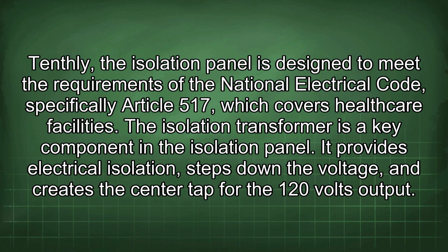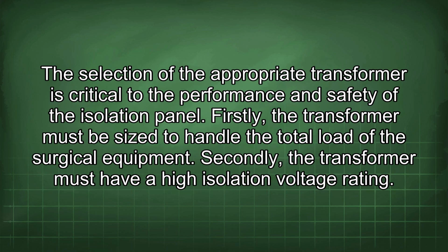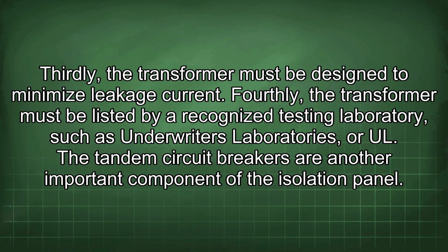The isolation transformer is a key component in the isolation panel. It provides electrical isolation, steps down the voltage, and creates the center tap for the 120 volts output. The selection of the appropriate transformer is critical to the performance and safety of the isolation panel. Firstly, the transformer must be sized to handle the total load of the surgical equipment. Secondly, the transformer must have a high isolation voltage rating. Thirdly, the transformer must be designed to minimize leakage current. Fourthly, the transformer must be listed by a recognized testing laboratory, such as Underwriters Laboratories, or UL.